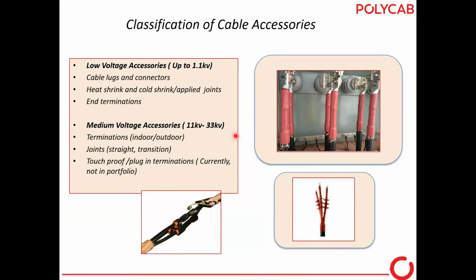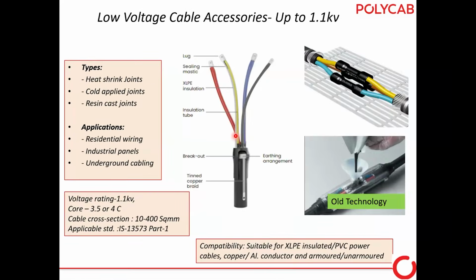Now let's come to the classification of the cable accessories. Generally, whatever we are discussing is for armored cables actually. So 1.1 kV low voltage and medium voltage is how we broadly classify the cable accessories. Low voltage is up to 1.1 kV, and medium voltage is 11 kV, 22 kV, 33 kV. These are the medium voltage cable accessories. So we generally classify these cable accessories in two voltage classes. Let's see low voltage cable accessories.